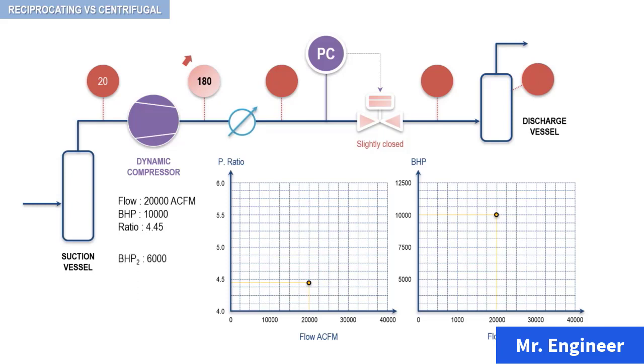Why is that? Because the characteristic performance curve of any centrifugal compressor is different from a reciprocating compressor. A reciprocating compressor curve is essentially vertical, since the actual volume flow is constant, and therefore the brake horsepower will increase as the pressure ratio does. In the case of a centrifugal compressor, increasing the pressure ratio will result in a lower compressor flow rate, since the only way a centrifugal compressor can develop a higher pressure ratio is at a lower gas velocity — in other words, at a lower flow rate. Simply stated, the longer the gas is in contact with the centrifugal compressor blades, the higher the pressure ratio. For a centrifugal compressor, this means the flow rate must decrease.